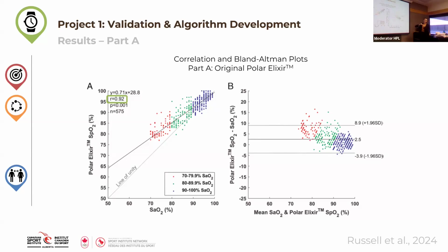So if all our data points fell on the line of unity, everything would be perfect and we could go home. But we can see that as we go from blue to red, it gets farther and farther away from that line of unity. And in particular, it is above the line of unity, showing that the SpO2 sensor seems to be overestimating, like we saw in that time series graph. And then, backing up, the Pearson correlation is quite high, 0.92. Like I mentioned, you could have a high correlation, but that does not mean it's an accurate device.